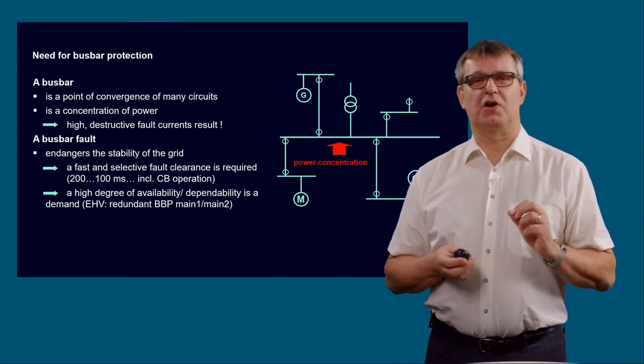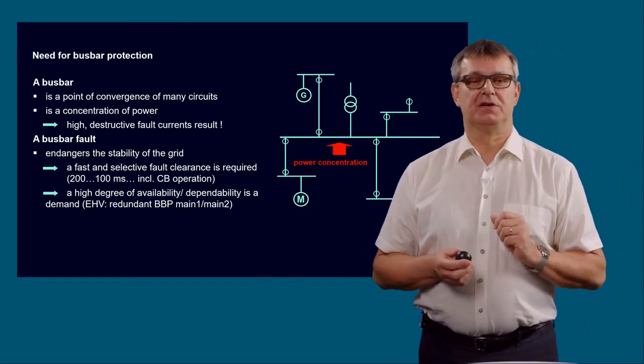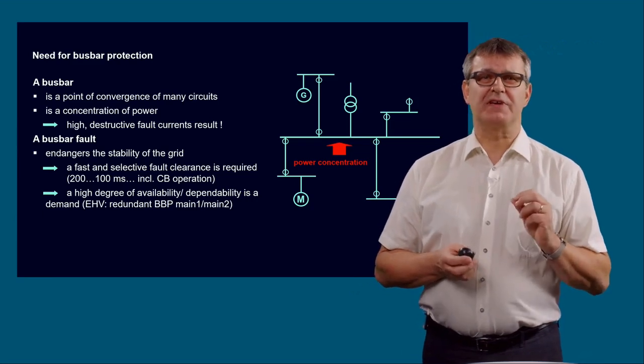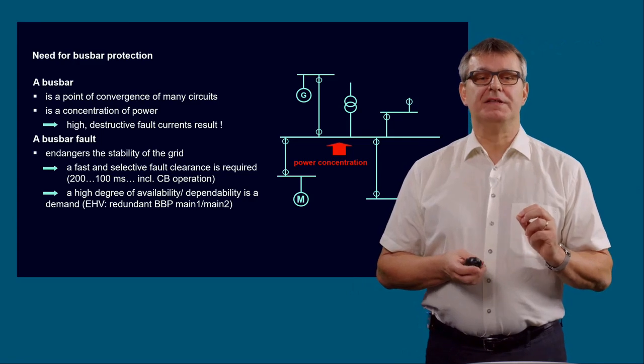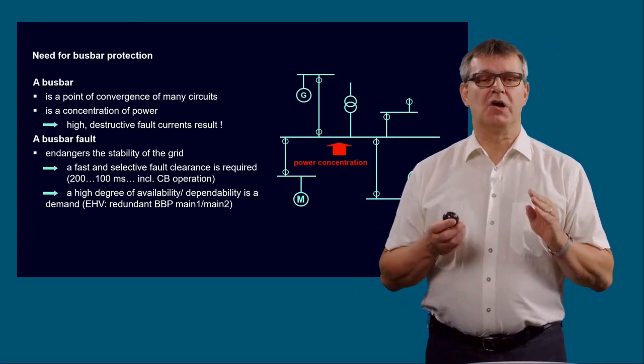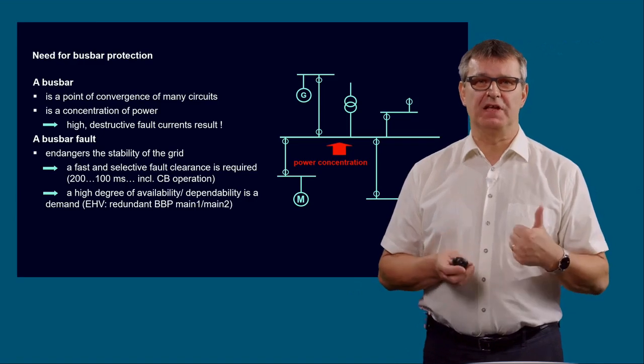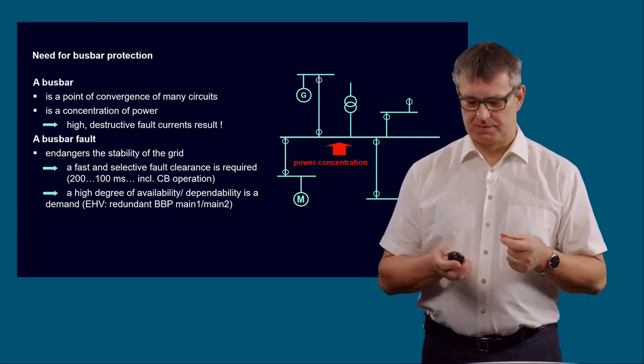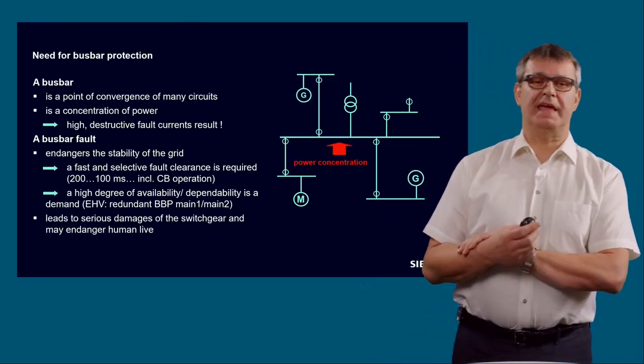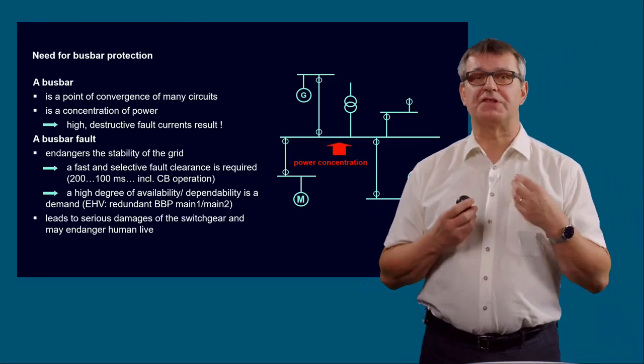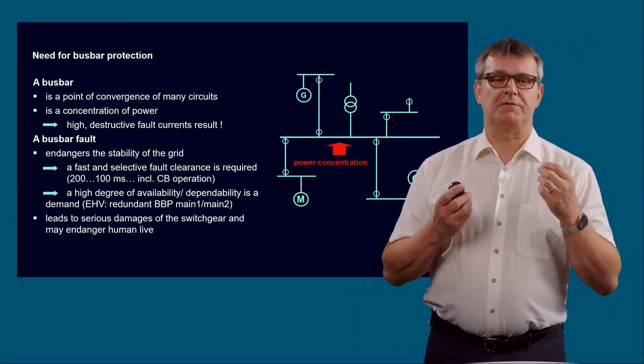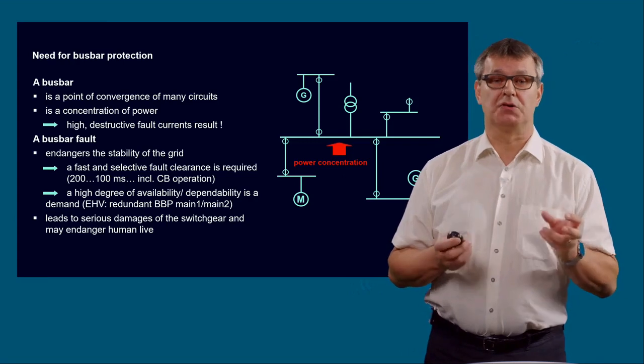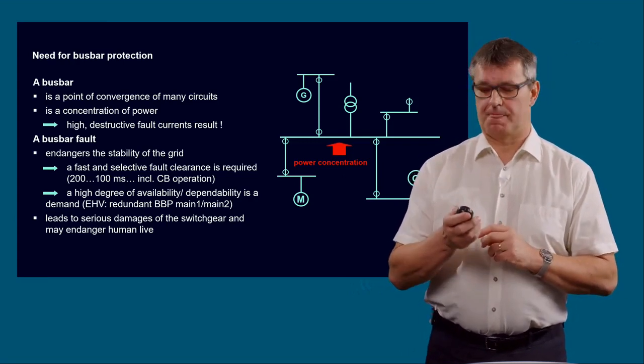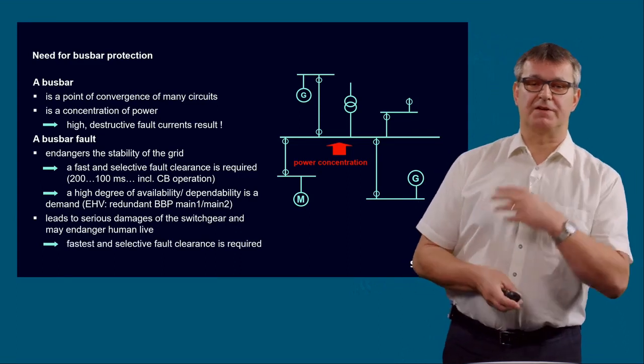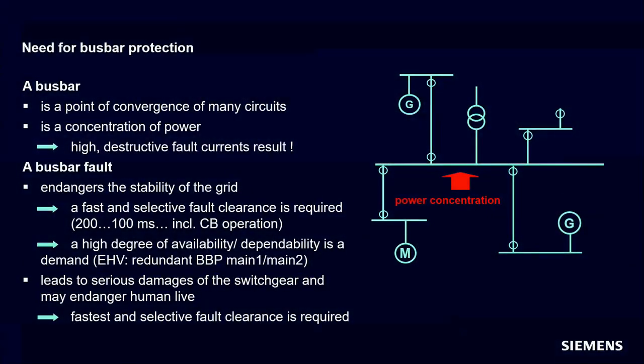Also, we need a high degree of availability and dependability. And especially at extremely high voltage levels, in the meantime we also have more and more redundant busbar protection. That means a main 1 and a main 2 busbar protection system. And a busbar fault, because it's very destructive, can lead to very serious damage to the switchgear and may also endanger human life. And therefore, once again, a very fast and selective fault clearance by busbar protection is necessary.